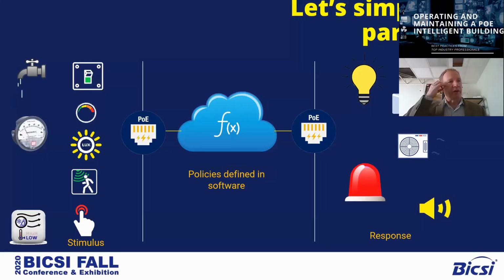In a controls world, one thing I often encourage is to look at controls as breaking down into, on the left-hand side, stimulus, and on the right-hand side, response. Stimulus may be a wall switch press, an occupancy event, a light level reading, a pressure sensor on a valve, or an air pressure sensor. On the right-hand side is the response: a light turns on, HVAC turns on or off, an email is sent out, or an alarm is sounded. The beautiful thing about Power over Ethernet is everything between those two can now be completely software defined—for example, connecting a temperature sensor through an outside weather forecasting app to affect and adjust the HVAC accordingly. This technology, more than any other, has the ability to unify all of these, again through open standards.